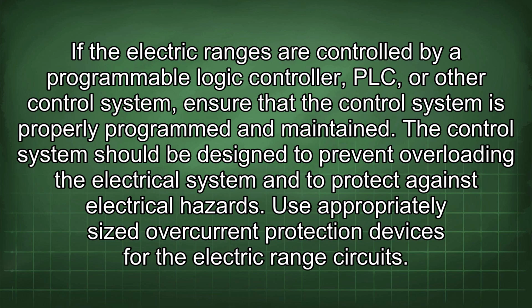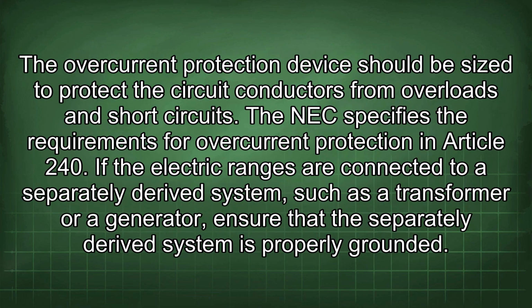Use appropriately sized overcurrent protection devices for the electric range circuits. The overcurrent protection device should be sized to protect the circuit conductors from overloads and short circuits. The NEC specifies the requirements for overcurrent protection in Article 240.